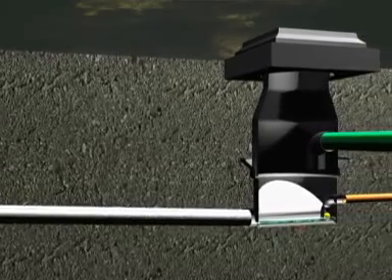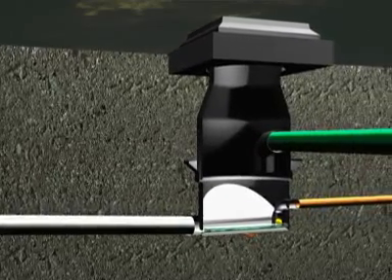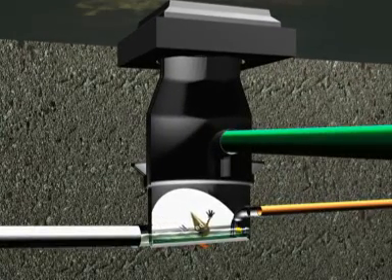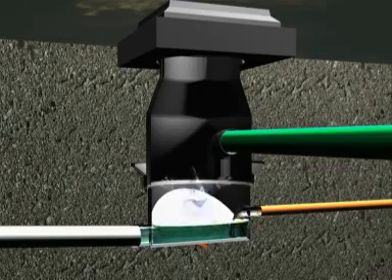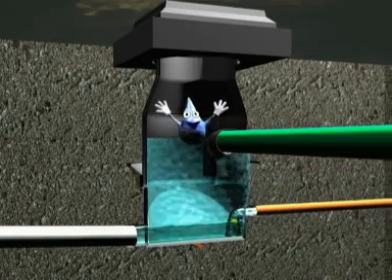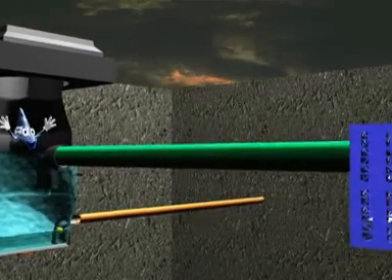The separating chamber is fitted with a drainage limiter that ensures that the initial polluted rainwater is discharged to the sewage drain. The relatively clean rainwater is then drained separately through a green pipe for clean rainwater to the infiltration system or surface water.